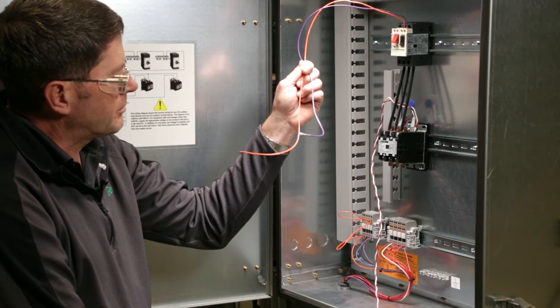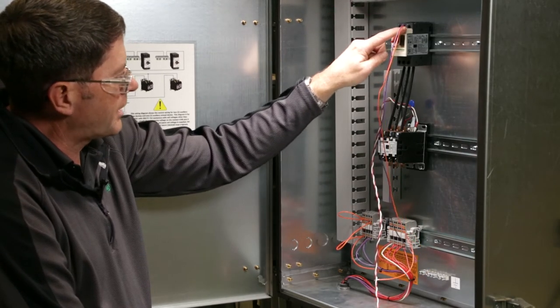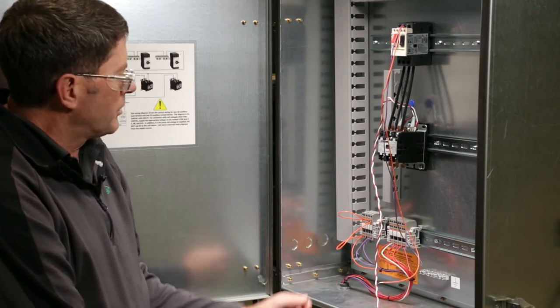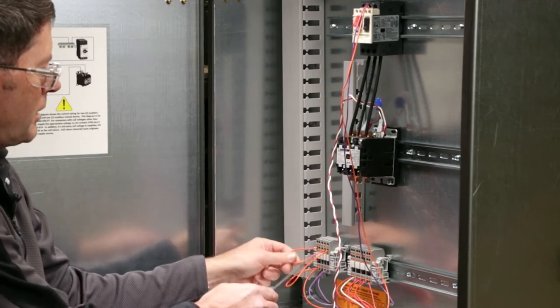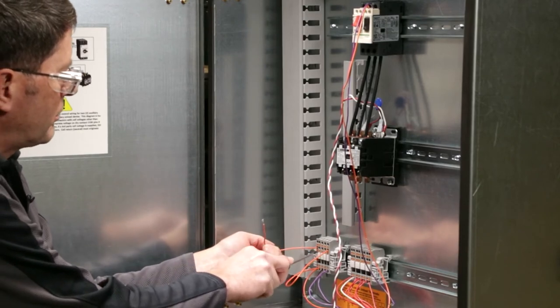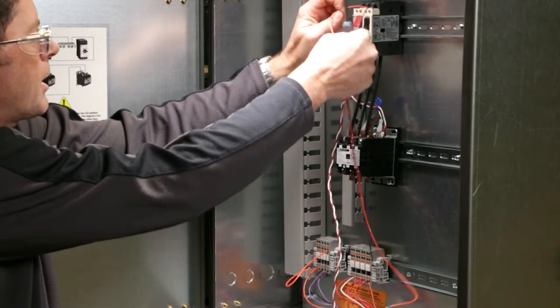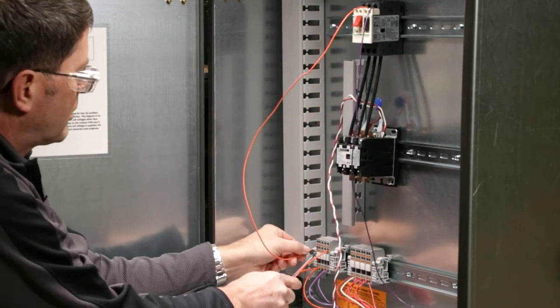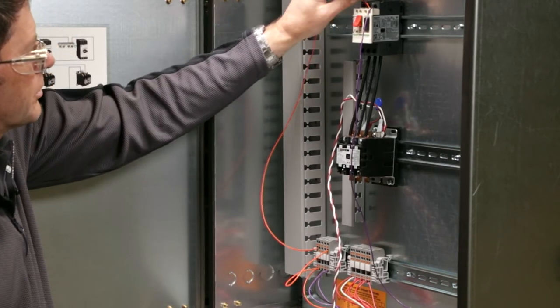The first one, we'll need to use some wiring to go to the auxiliary contact. And that's going to be used to do our motor overload circuit. So coming from the factory, that'll be circuit 49D and we'll have a jumper wire installed in there. So what we'll need to do is remove that jumper wire and you're going to need to supply our 24 volt DC power circuit 18 to one side of the auxiliary contact.